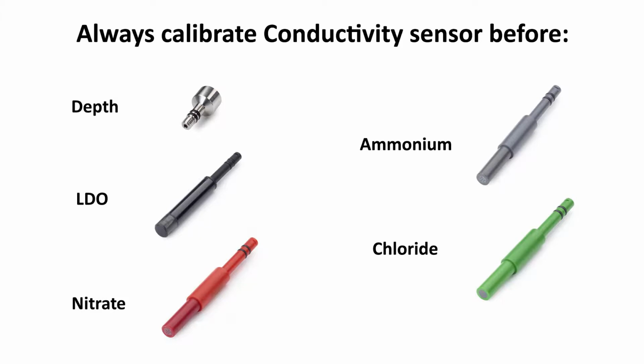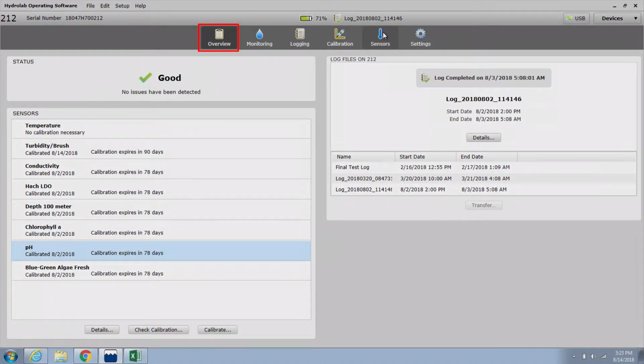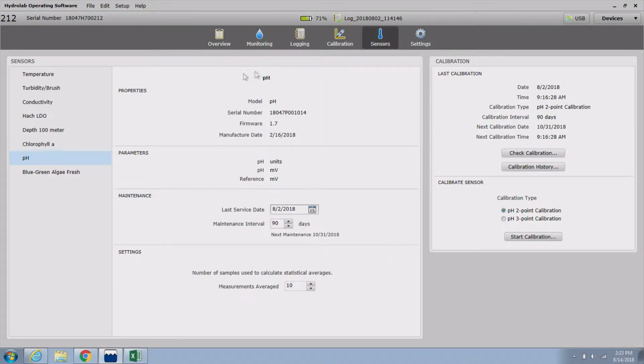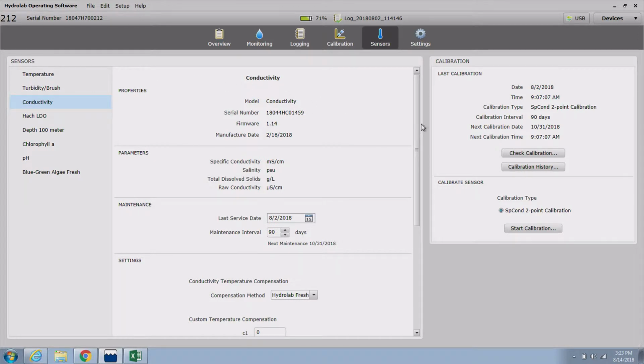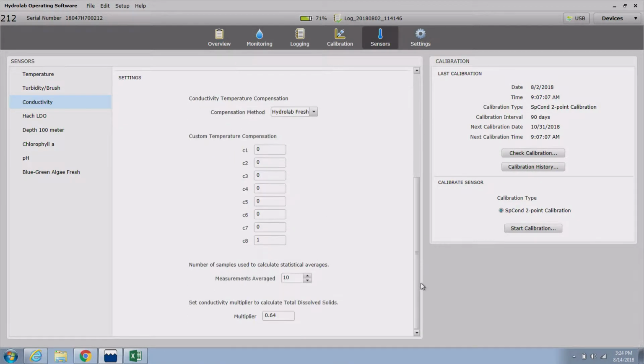Calibration. Important. The conductivity sensor requires a 2-point calibration. Calibrate conductivity before LDO, depth, nitrate, ammonium, and chloride sensors, as these sensors are dependent on the conductivity readings. Ensure that the desired temperature compensation method has been selected for your application in the Sensor tab of the Hydrolab operating software. The default compensation method is Hydrolab Fresh.